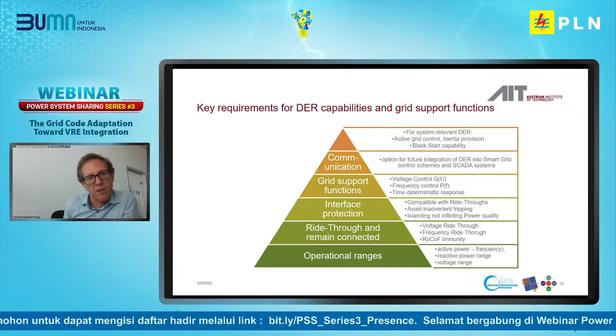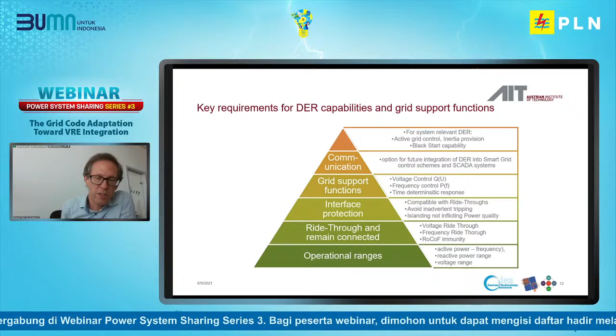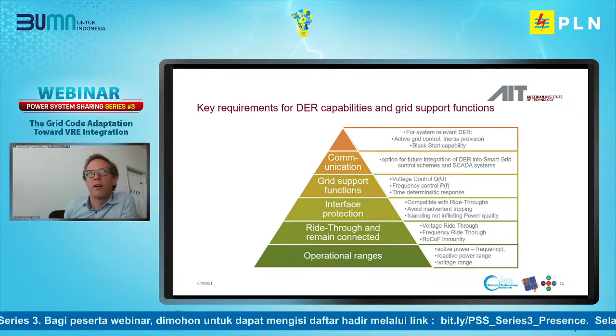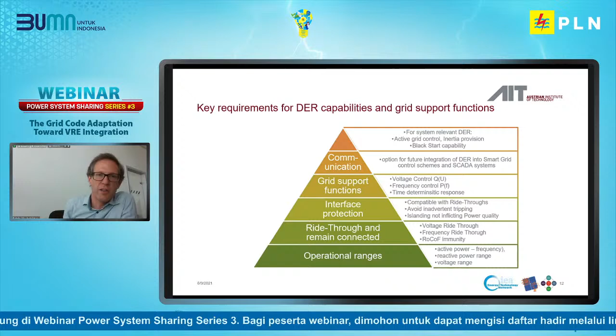Then the codes also include protection requirements, for the interface protection. When you design a grid code, it's important to make sure that these interface protection requirements are compatible with the ride-through requirements. Moving to the top of the pyramid, we have grid support functions, which today are mainly related to voltage support and frequency support. On the very top, for system-relevant generation, there are requirements for communication. For some generators, and this is a bit of an outlook to the future, we expect generators providing active grid control, inertia, and also black start capabilities.